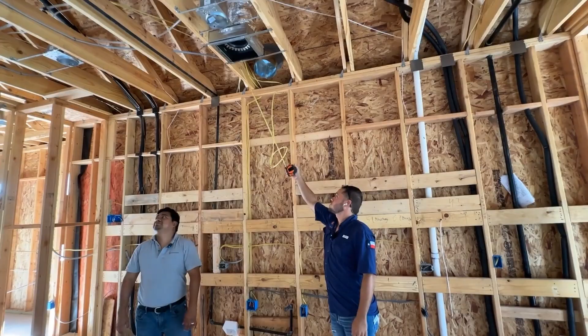The makeup air kit we were showing you earlier is pretty much this duct right here, or this vent. So this is going to be your vent hood here. We always try to put the makeup air vent as close as possible, and actually in line with the vent hood, so it doesn't look too bad. What happens is the makeup air kit opens, so all the hot air comes straight down and back outside, so you're not removing air from inside the house to the outside.